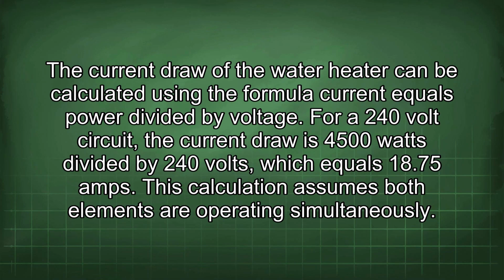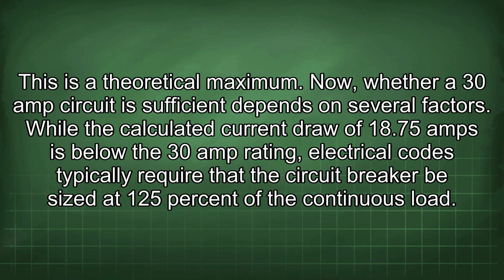The current draw of the water heater can be calculated using the formula current equals power divided by voltage. For a 240 volt circuit, the current draw is 4,500 watts divided by 240 volts, which equals 18.75 amps. This calculation assumes both elements are operating simultaneously. This is a theoretical maximum. Now, whether a 30 amp circuit is sufficient depends on several factors.